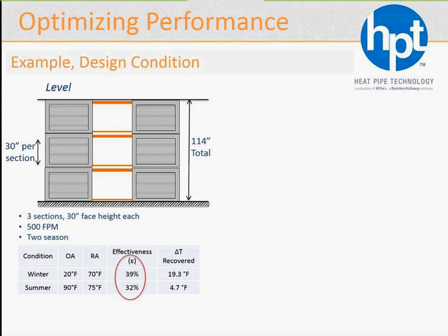Effectiveness. This is one product that is sensitive to temperature differential, so it tends to vary summer and winter. In winter we have the larger delta Ts, so effectiveness is 39% for 6 rows at 500 feet per minute. You could lower the face velocity, and you can actually get the recovery or effectiveness to go a little bit higher. You can also spray the exhaust side, the direct evap cooling, and enhance that as well.